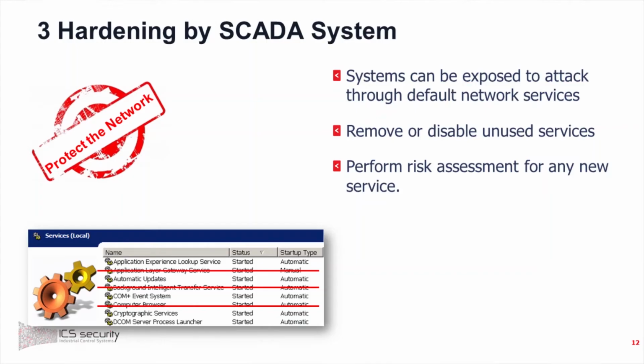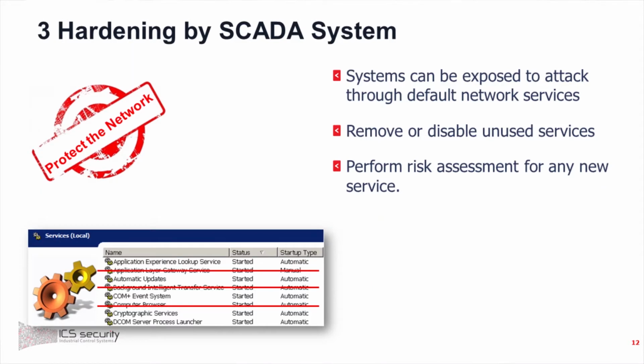We'll explain more later. Commandment 3: Harden the SCADA system. Systems can be exposed to attack through default network services. Remove or disable unused services and network daemons to reduce the risk of direct attack. SCADA servers and clients don't need any application or software besides the HMI software, its drivers, and SQL Server databases—no other service needs to run. So if you use something like Sparta, for example, it blocks any process from running except the HMI processes. For any new service, a threat risk assessment of the consequences of allowing that service or feature must be conducted before adding it to the system.